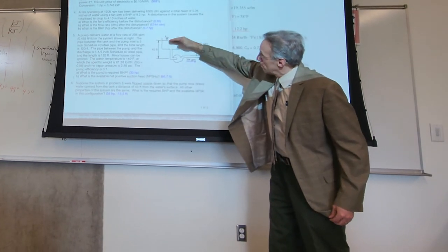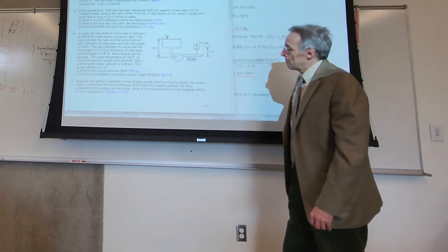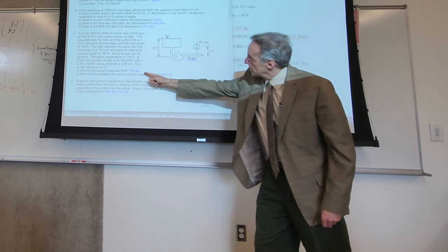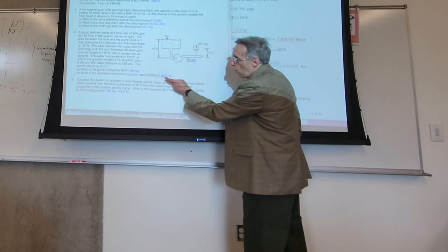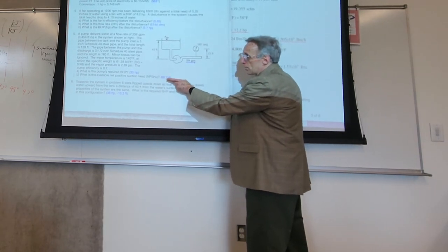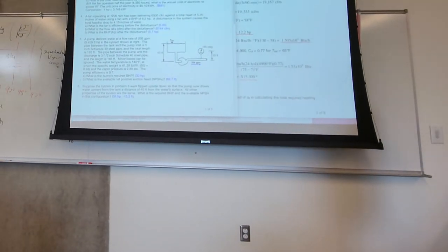This one, you're really good. Having your source above the pump usually protects you from cavitation issues in the pump. I think here we're way up. Of course, you have to compare this with the required suction head, and that's going to be on the manufacturer's pump curve, at 66.7. That should keep you well above the requirement.